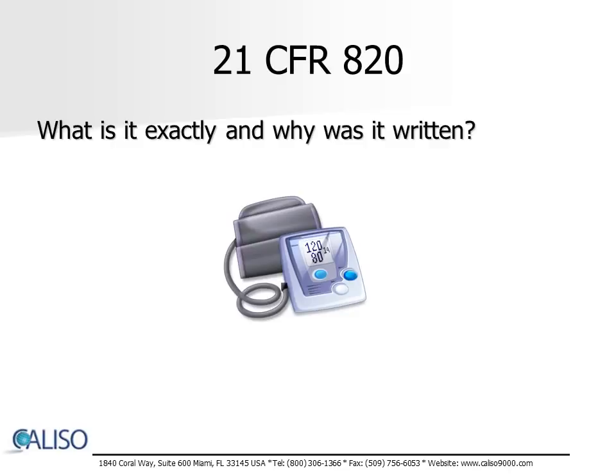21 CFR 820 is the United States regulations equivalent to the European standard ISO 13485:2003 in that they are both written specifically to dictate or set forth the requirements by which a medical device is designed, developed, manufactured, and monitored. And by monitor, I mean how complaints are handled.